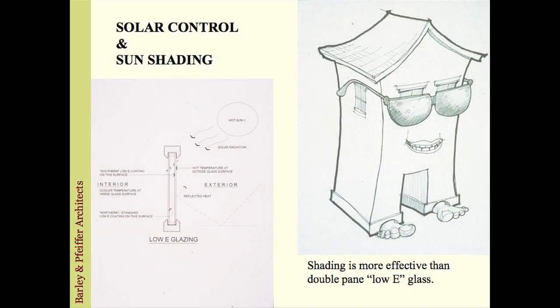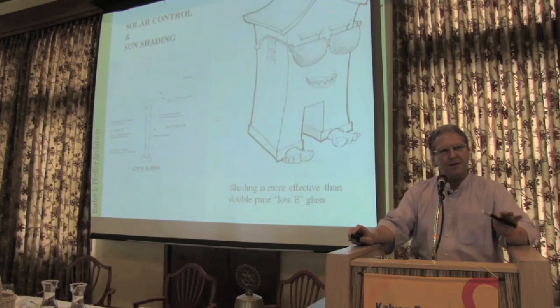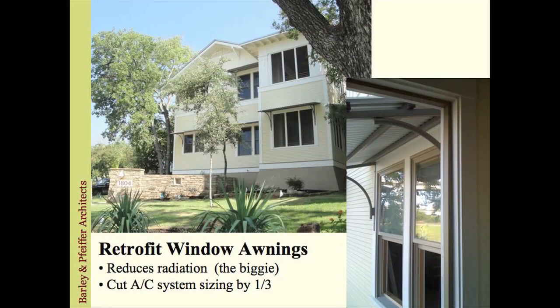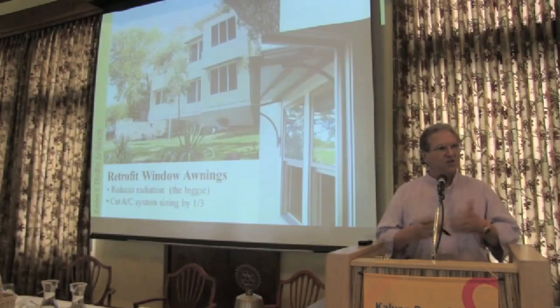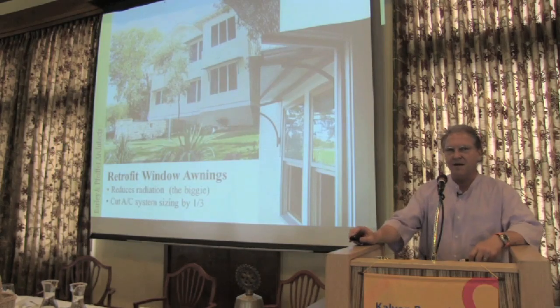Shading your windows is probably the most effective thing you can do, next to building a tight house, so that it doesn't get bombarded particularly by the afternoon sun. Low-e glass does help, but nothing like a good old-fashioned awning to shade the windows. This is an old home we renovated on 6th Street — these awnings alone cut the air conditioning load by a third, just by keeping the sun off the windows and preventing radiation from heating up the inside of the house.